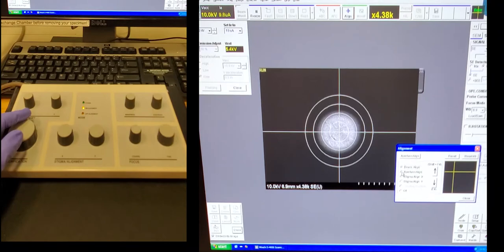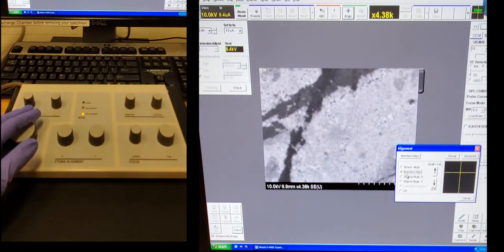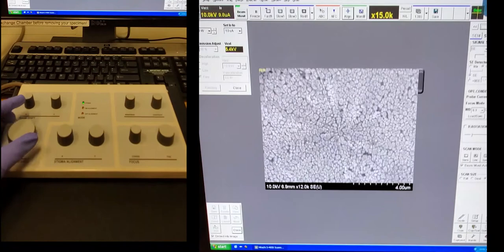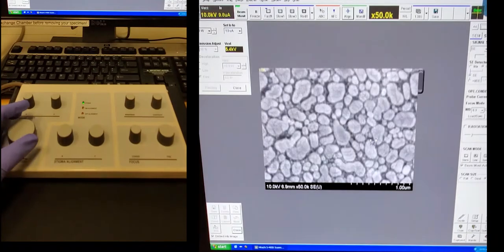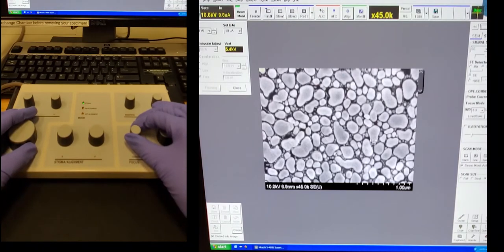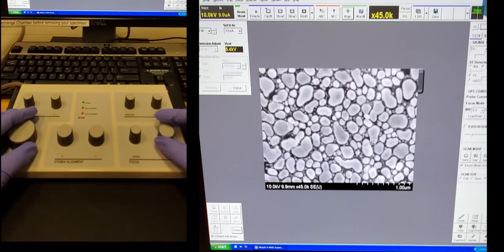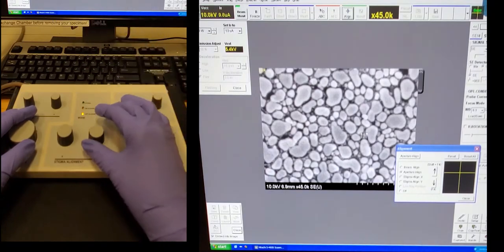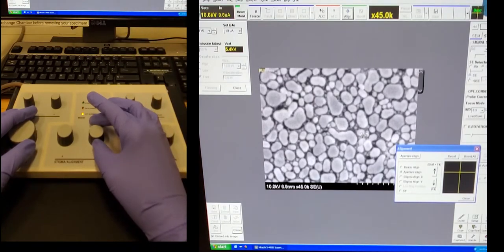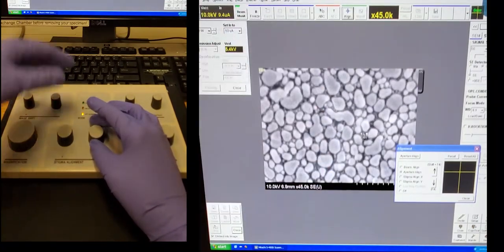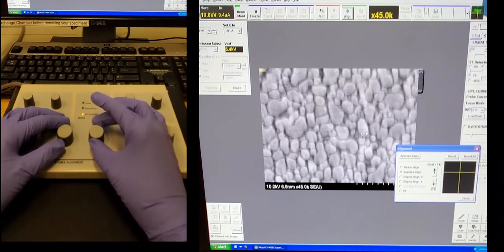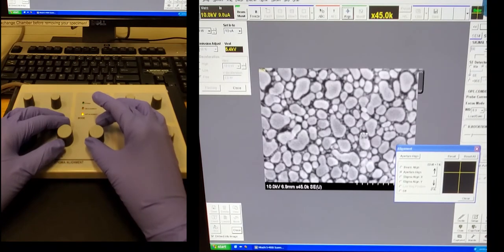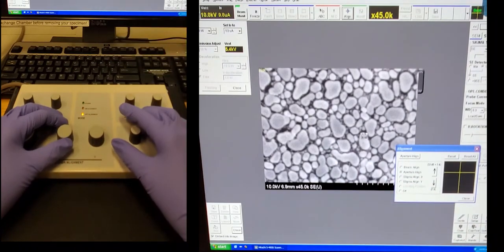So go down the list. If it pops you back out to a lower mag, just close the box and zoom back in. It's a glitch that doesn't happen every single time. We'll open the align again. So we are checking to basically minimize the wobble. You see there's a lot of y movement, so I'm going to correct the y knob here. And you see as I go in this direction, the wobble gets less and less. That is the goal is to minimize it in both the x direction and the y.